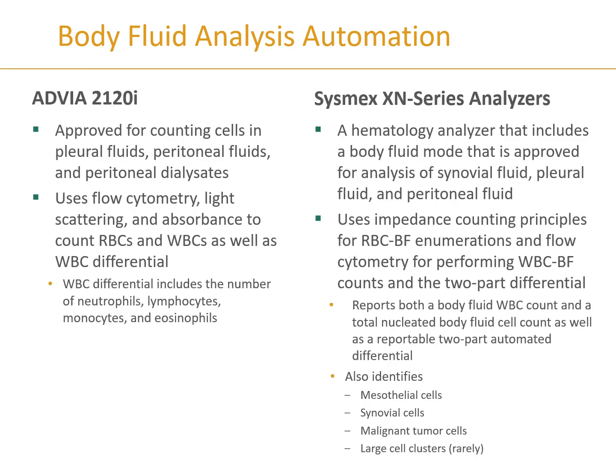The ADVIA is capable of performing cell counts on pleural fluids, peritoneal fluids, and peritoneal dialysis fluids. It uses flow cytometry, light scattering, and absorbance for white blood cell and red blood cell counts, and also performs a differential count to categorize white blood cells.